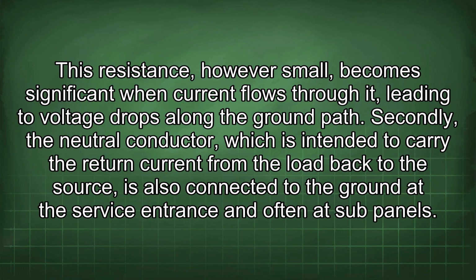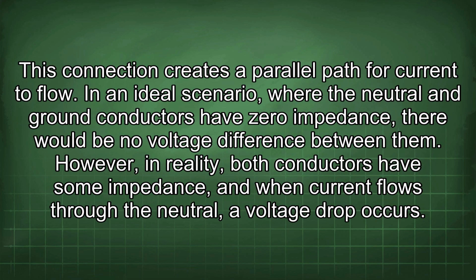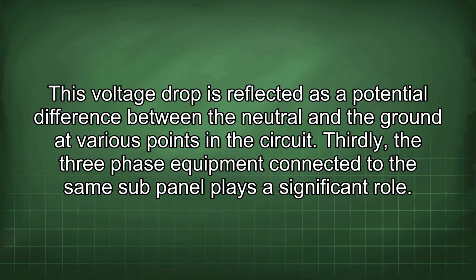Secondly, the neutral conductor, which is intended to carry the return current from the load back to the source, is also connected to the ground at the service entrance and often at subpanels. This connection creates a parallel path for current to flow. In an ideal scenario, where the neutral and ground conductors have zero impedance, there would be no voltage difference between them. However, in reality, both conductors have some impedance, and when current flows through the neutral, a voltage drop occurs. This voltage drop is reflected as a potential difference between the neutral and the ground at various points in the circuit.